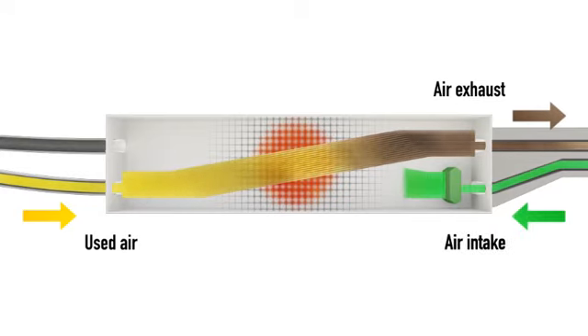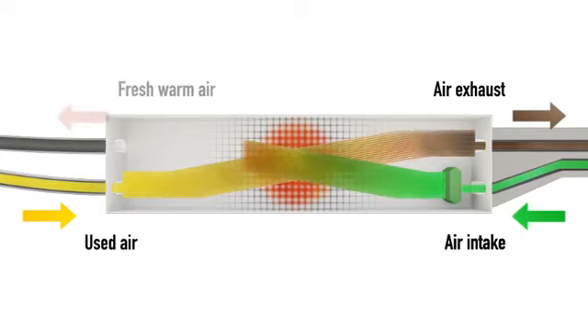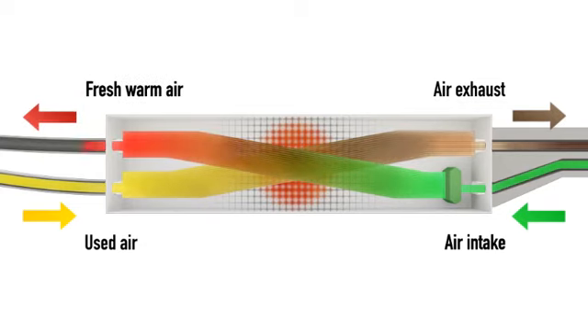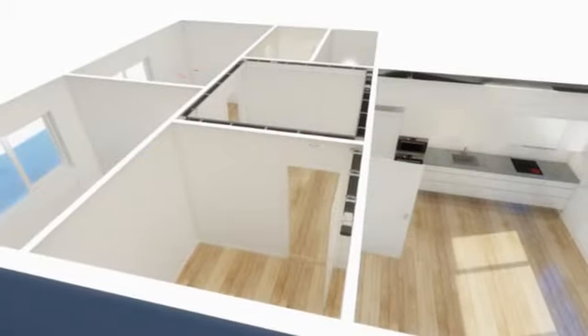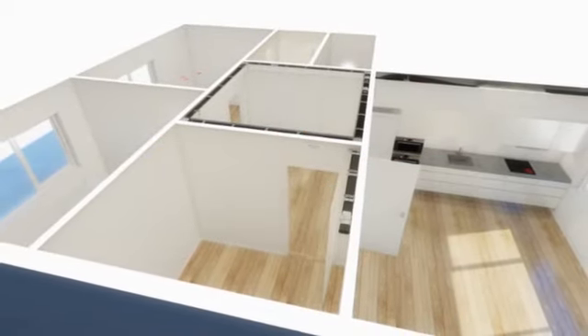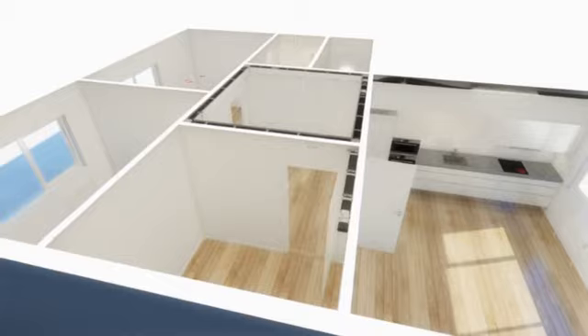Fresh air is sucked into the air handling unit via the air intake pipes. The air is then filtered and any dirt, pollen or pollution removed. From here, the air is fed through metal lamellas adjacent to the exhaust air pipes. The metal that was heated up by the exhaust air now warms up the fresh air, thereby recovering up to 80% of the energy needed to heat the flat.